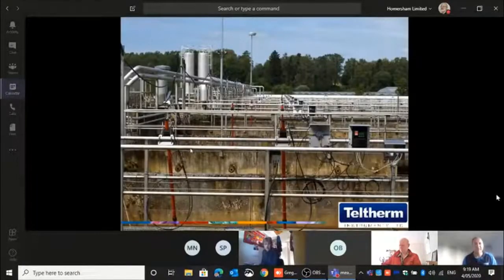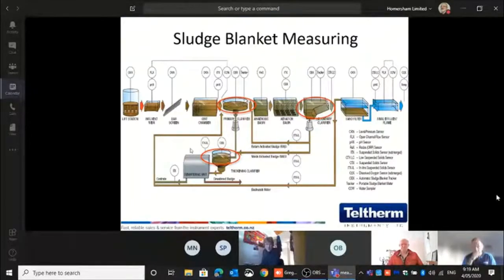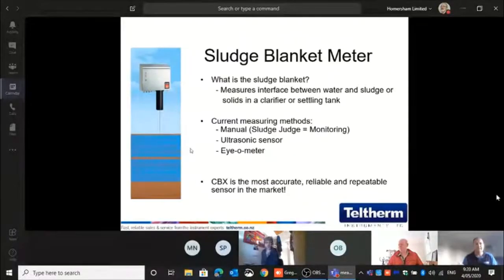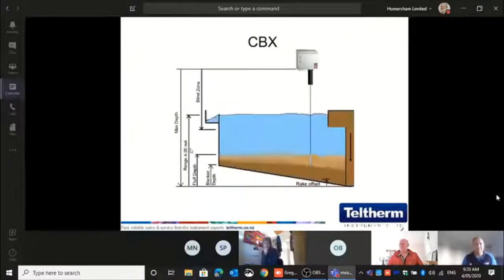This is what we would like to see in the wastewater treatment plants and water treatment plants. But yeah, this is a bit bigger. This is not us. Now your sludge blanket unit. The sludge blanket unit uses the same sensor. What people currently use is a sludge judge, ultrasonic sensor, or what we call an eye-o-meter. Basically, they just look. Well, that works most of the time. The problem is if you get a problem. This is what you want to see.